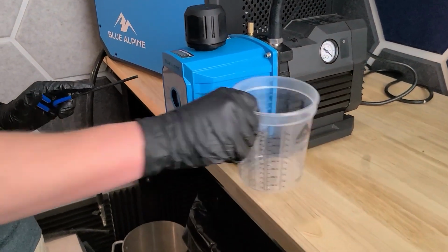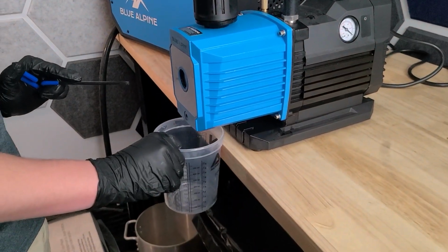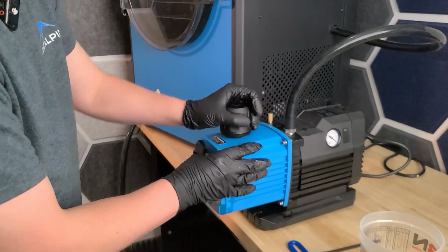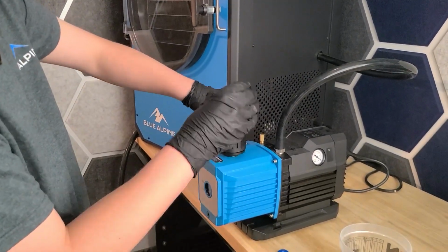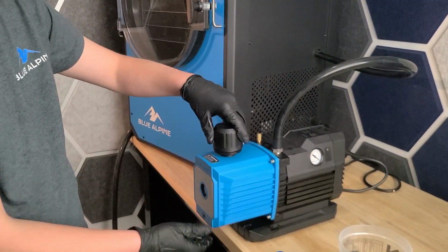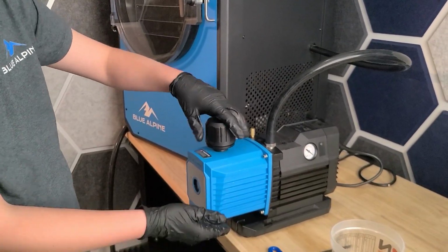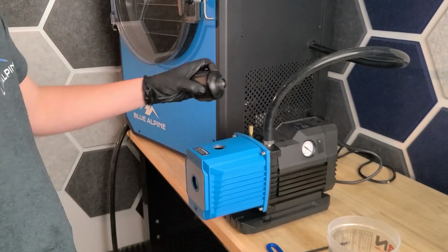The first step is going to be taking a plastic container and your Allen wrench and removing the oil out of your vacuum pump. It will drain to the bottom, so make sure you have your cup below. Also, when draining your oil, you're going to want to take off your filter. That filter will create a suction that won't allow any air coming through, so your vacuum pump oil will not drain quickly. So by removing your filter, your vacuum pump will just drain a lot faster.